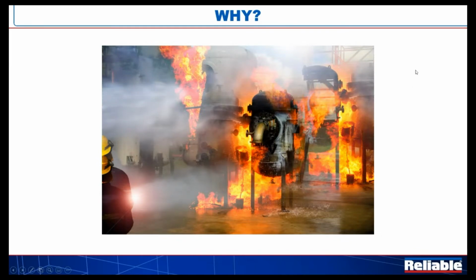So a second reason why we had exposure from, let's say, a wildfire. The second reason, 3D fires, right? A liquid fire that spills onto the floor. We talk about that when we talk about aircraft hangars. The volatile liquids running sideways and the need to then somehow attack those flames, and potentially from a much lower height than the sprinklers that might be at the roof, if there is indeed even a roof available.